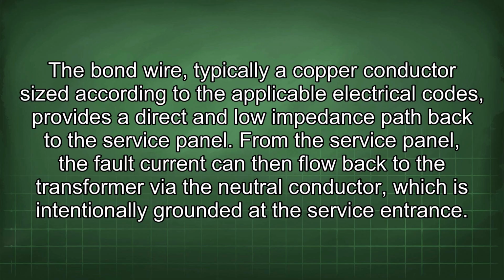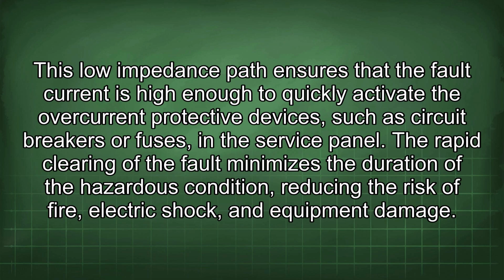The bond wire, typically a copper conductor sized according to the applicable electrical codes, provides a direct and low impedance path back to the service panel. From the service panel, the fault current can then flow back to the transformer via the neutral conductor, which is intentionally grounded at the service entrance. This low impedance path ensures that the fault current is high enough to quickly activate the overcurrent protective devices, such as circuit breakers or fuses, in the service panel.